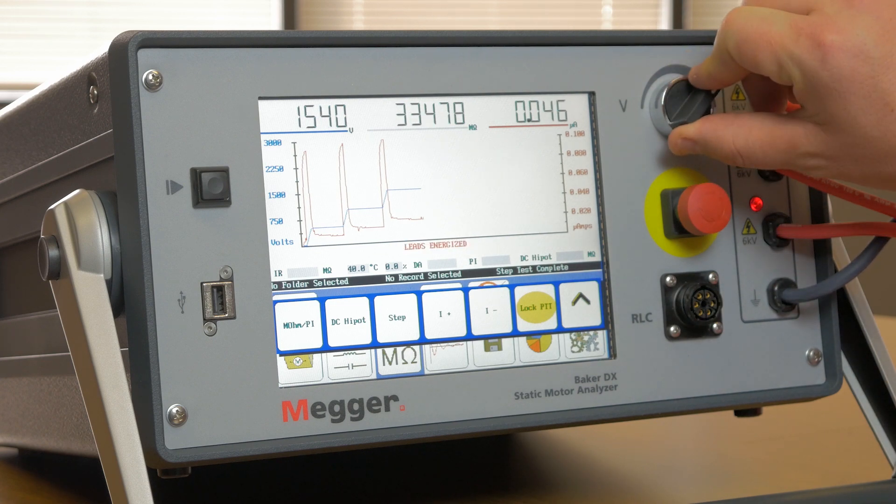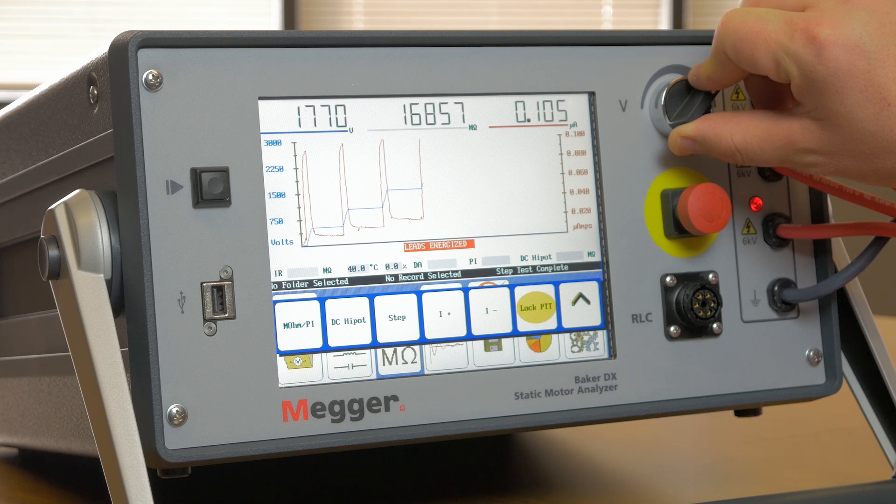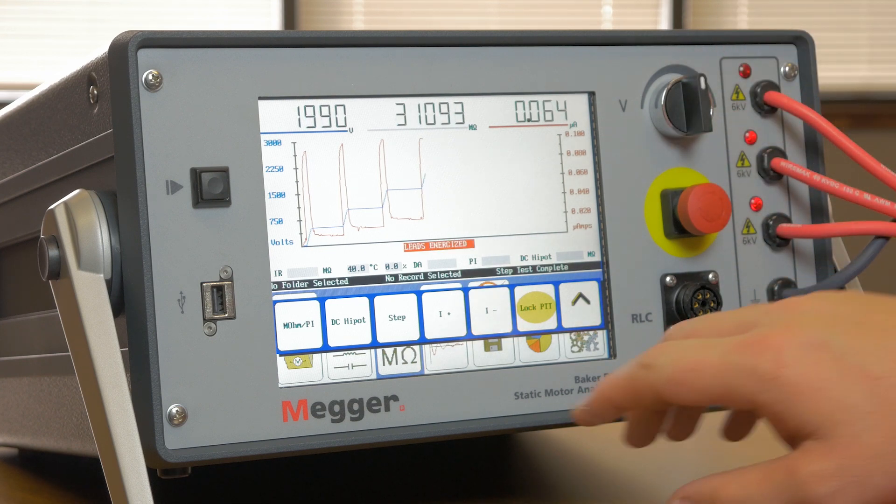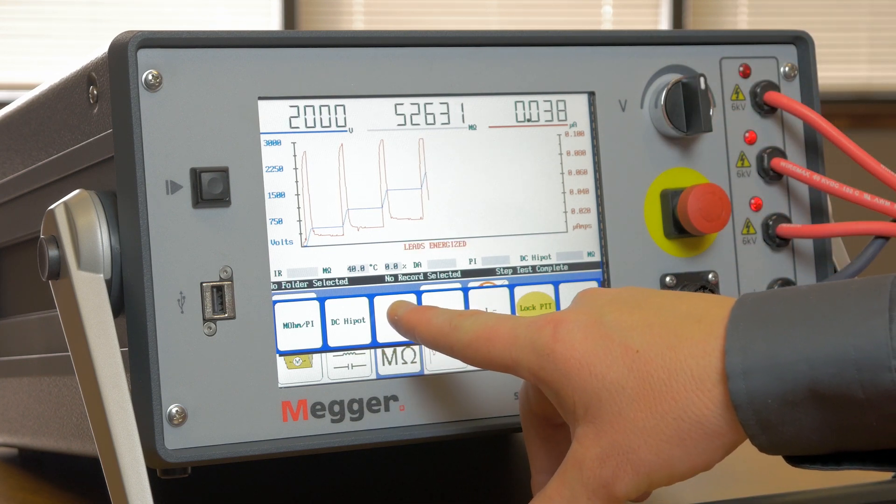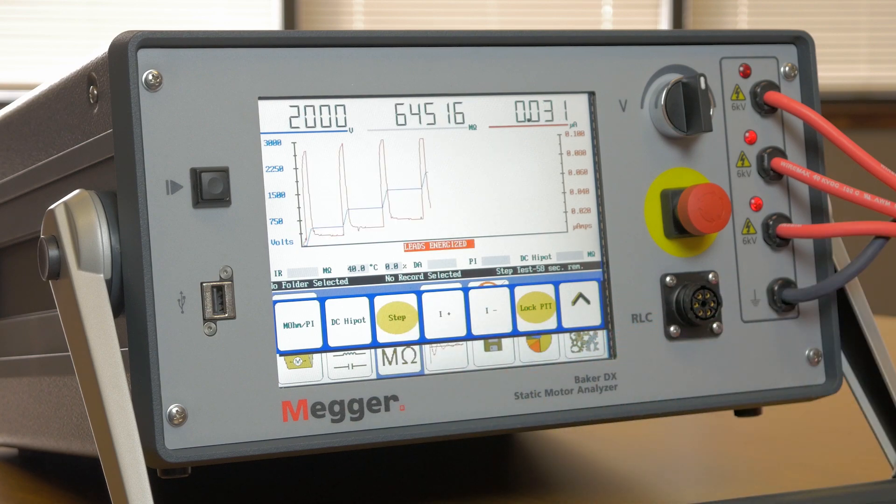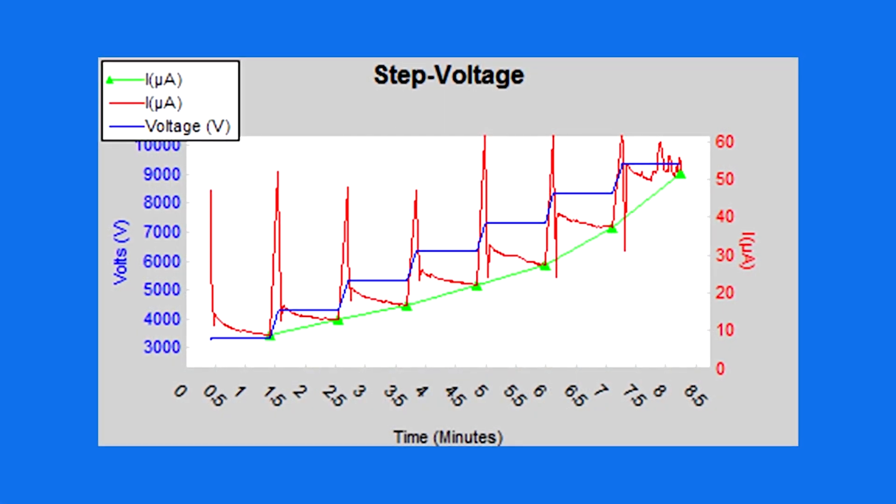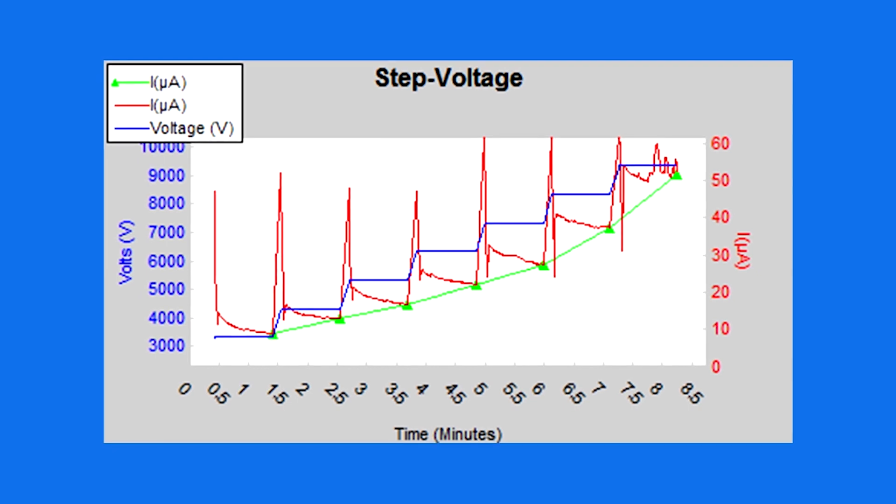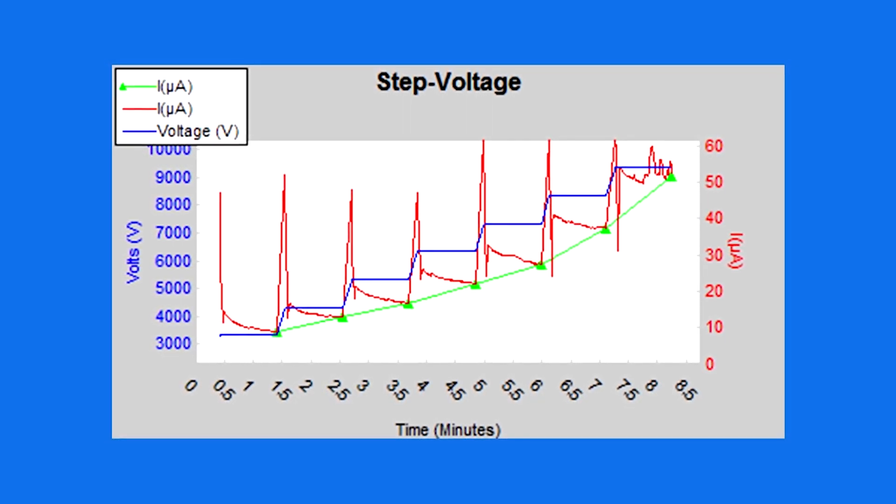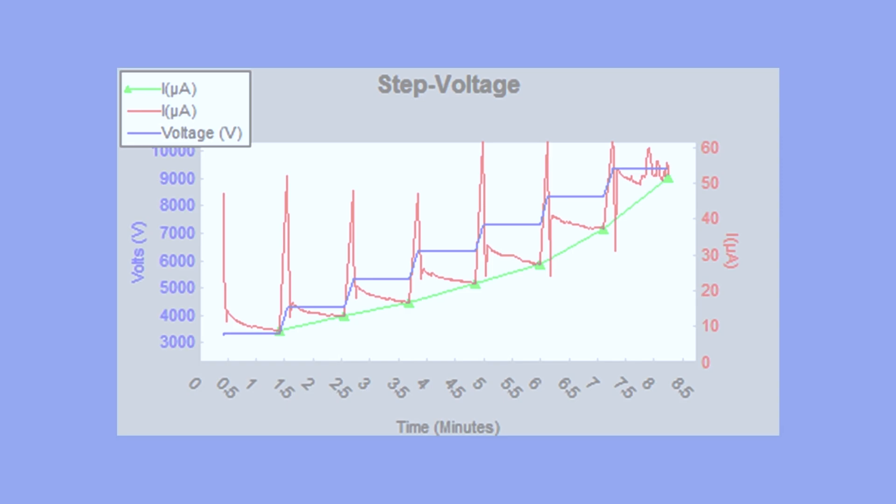To detect the non-linearity of weak ground-wall insulation, a higher-than-operating voltage is applied, but the voltage is applied as a steady ramp or in steps up to the final test voltage. Baker Static Testers plot the voltage applied and the resulting current flow. Where the ground-wall insulation is weak, the current will rise much more quickly than the voltage. This is the most complete test of ground-wall insulation.